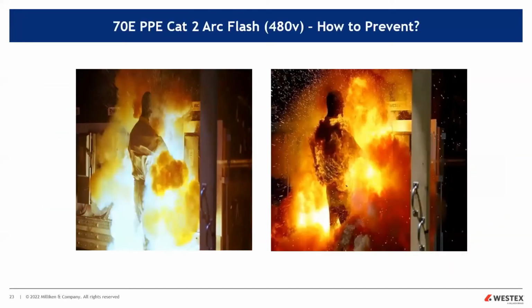Okay, so if I had one picture to show everyone why arc flash clothing and why, utilizing the hierarchy of risk controls on the pyramid here, it's because this picture here is sequential from left to right. So the preventative measures put in place were not good enough. The picture on the left shows an arc flash occurred. And then the protective measures on the right-hand side weren't taken. PPE wasn't worn because we see the arc flash is over, but we still have molten metal in the air. What do we see? The start of garment ignition. PPE was not worn. So this is exactly what we're trying to avoid. Pictures are worth 1,000 words. This looks like a catastrophic clothing fire.